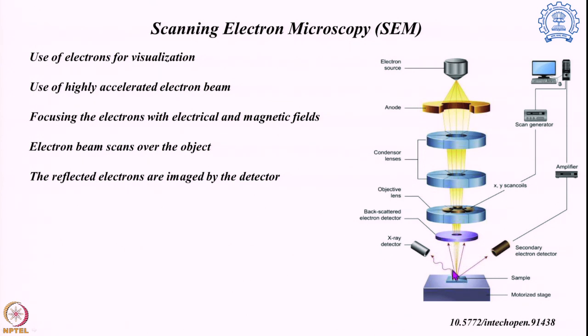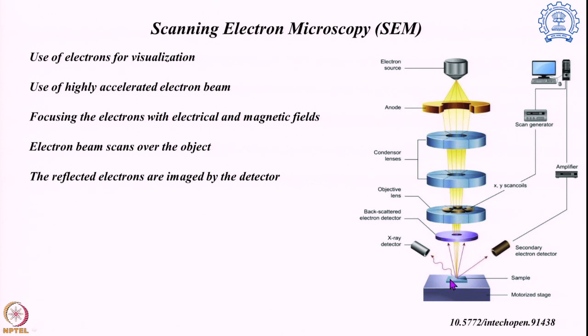When the sample is hit by the electrons, three different things happen. First, some electrons are scattered back toward the electron gun, and there is a detector for those back-scattered electrons. Some electrons are reflected and detected by the secondary electron detector, where signals are amplified and analyzed in the machine. Additionally, some electrons come out of the sample itself because the high-energetic electrons knock out valence and core-shell electrons from the sample.